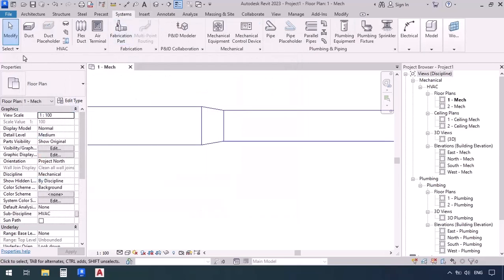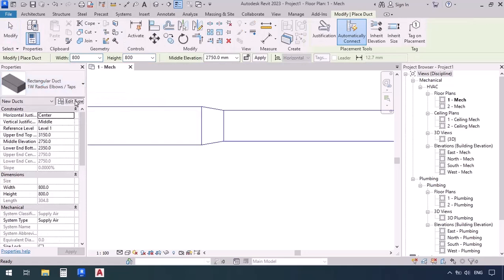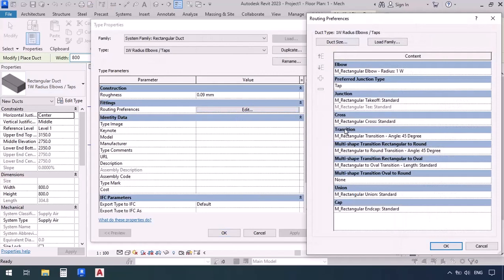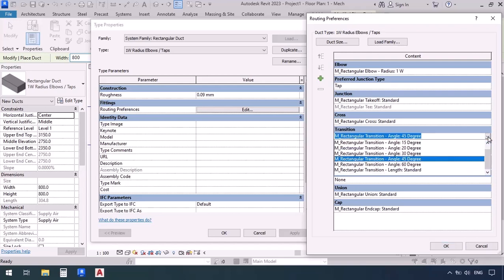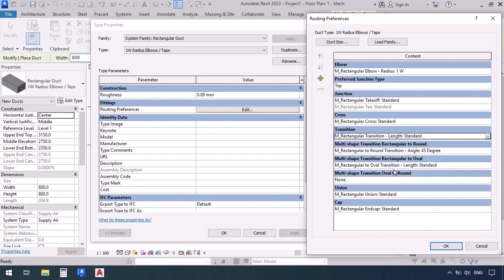Let's go to the Duct command via the Systems tab, use the same fitting we had, go to Edit Type and Edit. We want to say that from now on, if a transition is applied, we want to use the 'length' transition family — controlled by length, not angle. Note that we are editing this duct type, so this change will apply to all future ducts we draw. The previous ducts will remain unchanged.